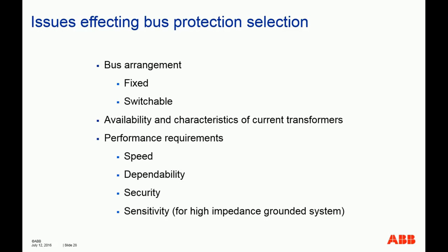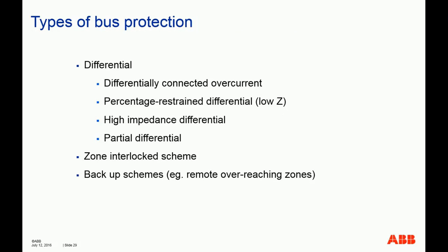Okay, some issues affecting bus protection selection. Bus arrangement, fixed or switchable, that's what we mentioned before. Availability and characteristics of the current transformer, that we covered, and some performance requirements: speed, dependability, security. In general, bus protection needs to operate fast for an internal fault and needs to be absolutely secure for an external fault. Different types of bus protection systems will be introduced later.